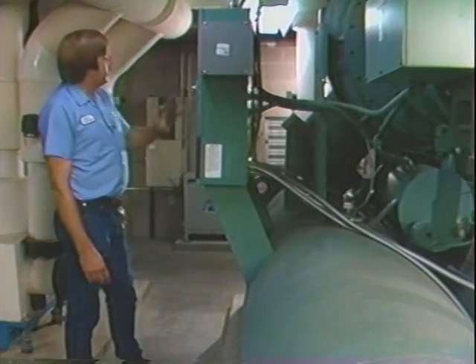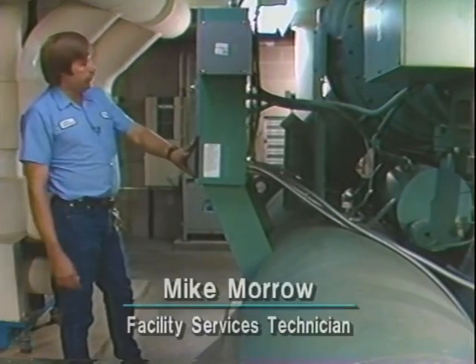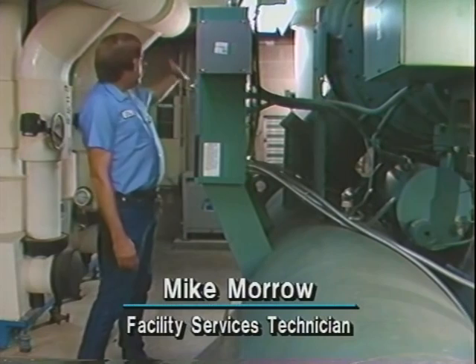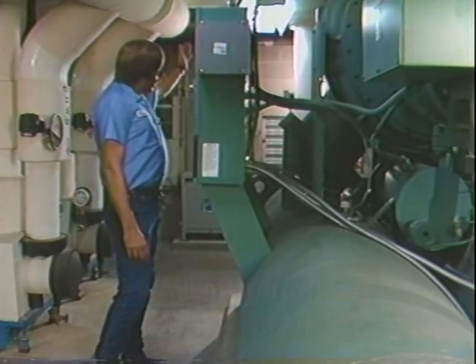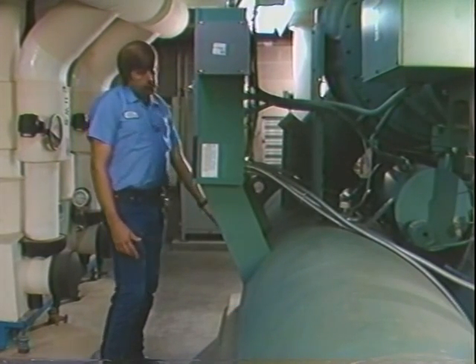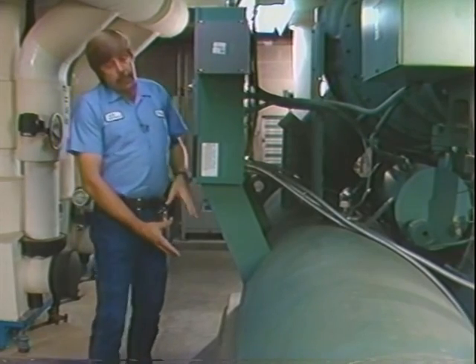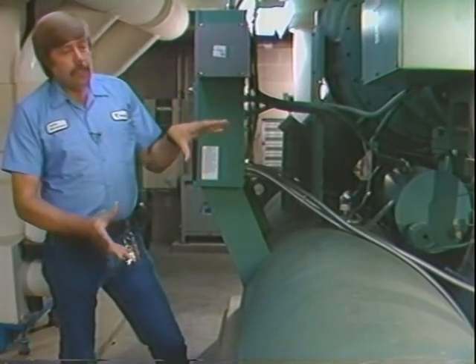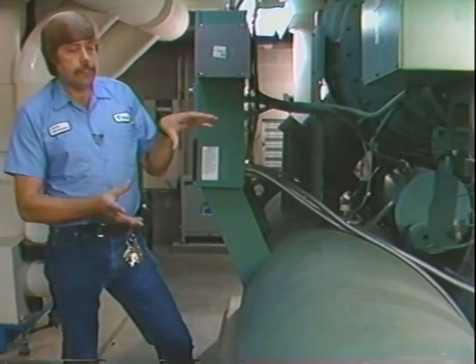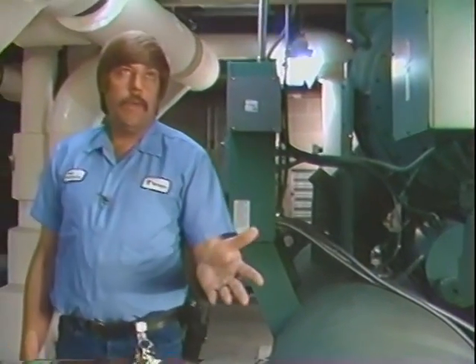Most of us know the Arizona sun is great for getting a tan, but it puts a real strain on energy demand. So, large buildings rely on highly efficient chilled water systems instead of traditional air conditioning units. At this location, we have a 300-ton chiller. We're taking water that's coming back from the buildings and bringing it into this end of the chiller barrel. In the chiller barrel, we have cold refrigerant that's chilling this water down to approximately 45 degrees.